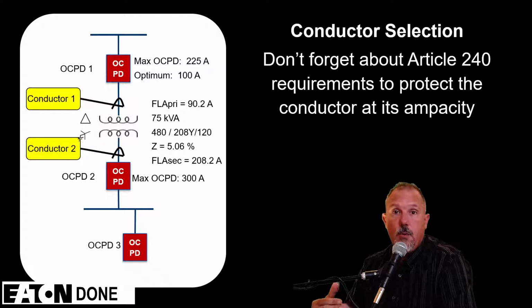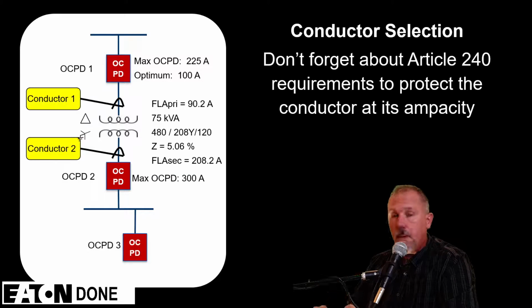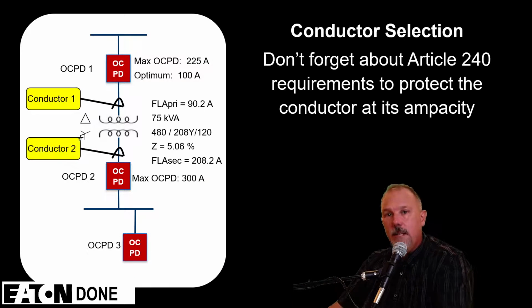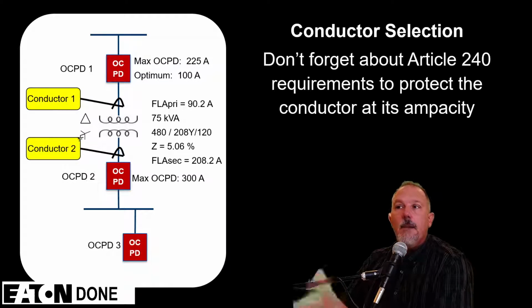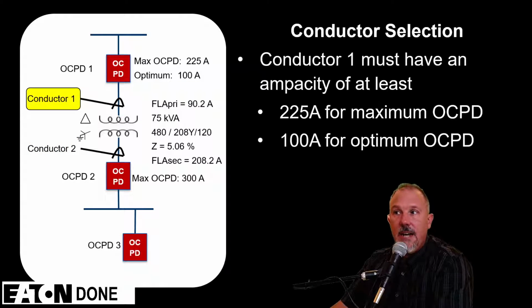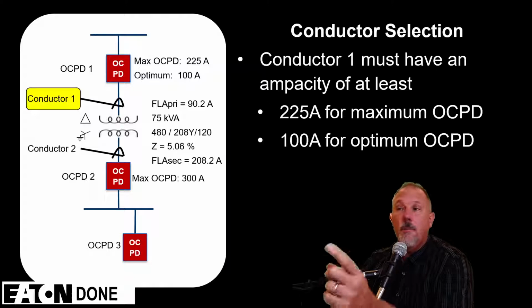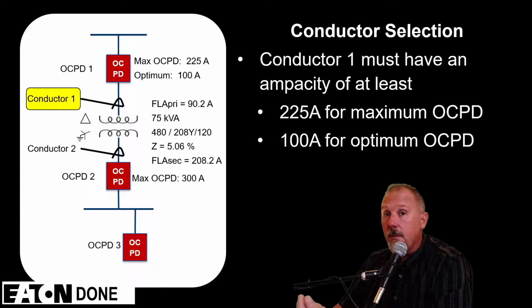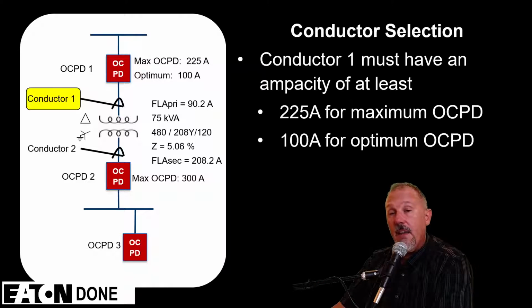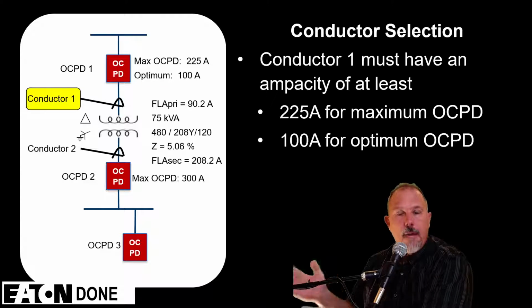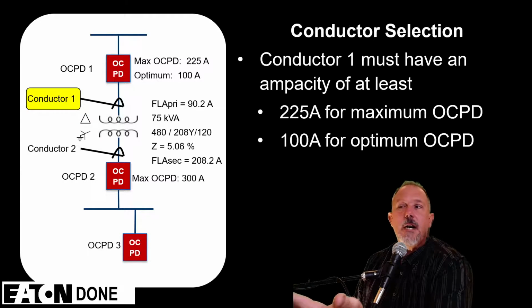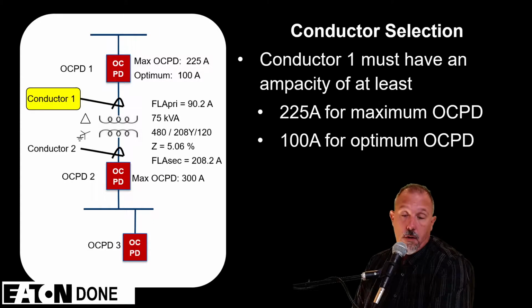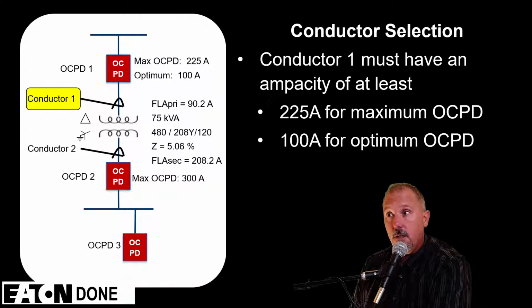Now, for sizing the conductors, this is really simple. If you've picked your overcurrent protective devices based upon inrush current, selective coordination needs, incident energy needs, etc., the size of the primary conductor is going to be the size of the primary overcurrent protective device. So if you picked a 225 amp breaker, you're putting 225 amps worth of conductor, even though you only have a full load amps of 90.2. If you picked a 100 amp breaker or fuse, then you're going to put 100 amps worth of conductor, regardless of what the full load amps is.